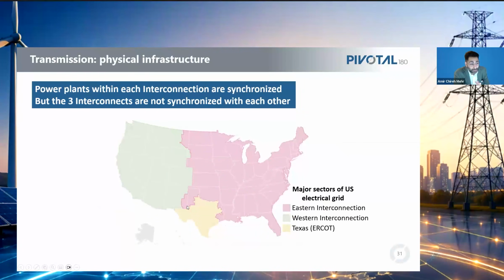Also because of the physical barriers. A good rule of thumb if you're building transmission lines historically was each mile might cost $1 million in terms of just the cost of building the transmission, the steel, the copper, whatever else is required to build the big towers and then build the cables across the top of them. And that can increase to $3 to $12 million if we're talking about, say, mountainous terrain, which is part of the reason why East and West are poorly connected. It's just geography. Geography is destiny.